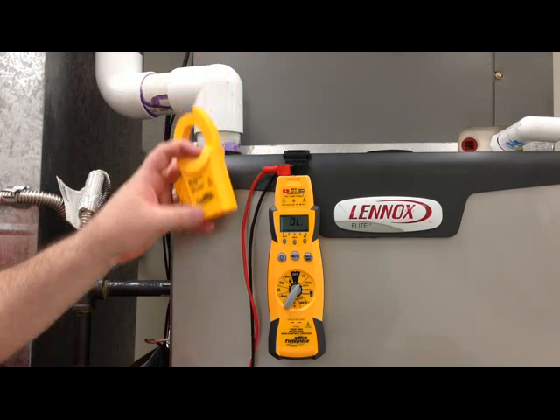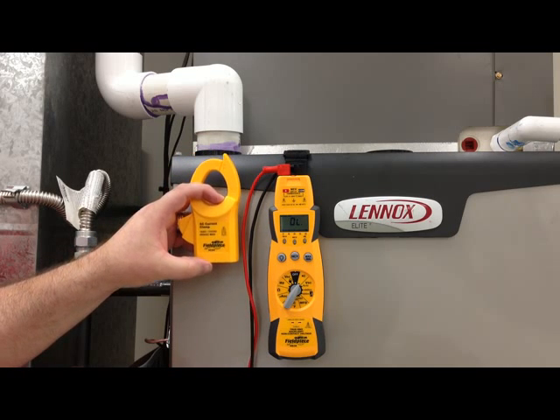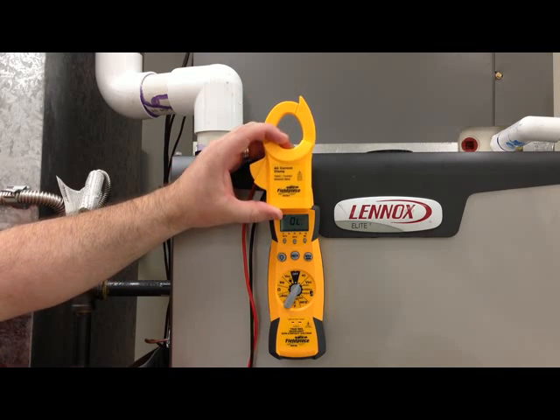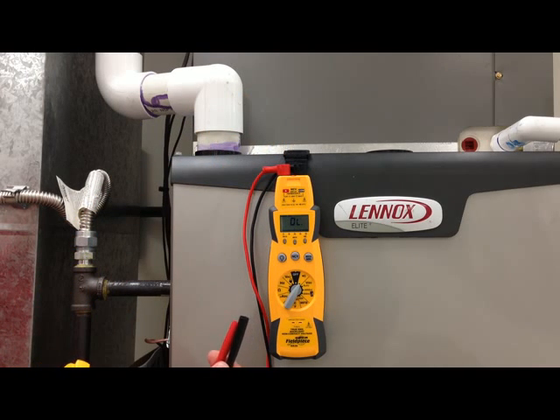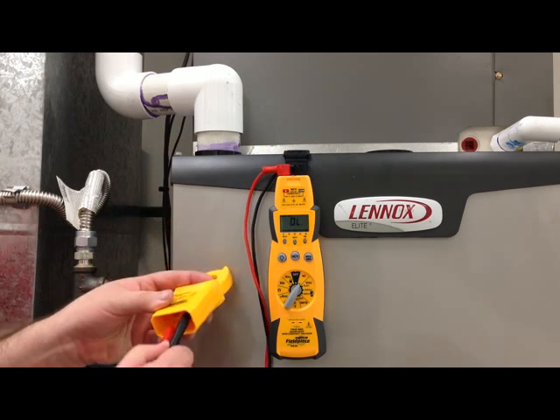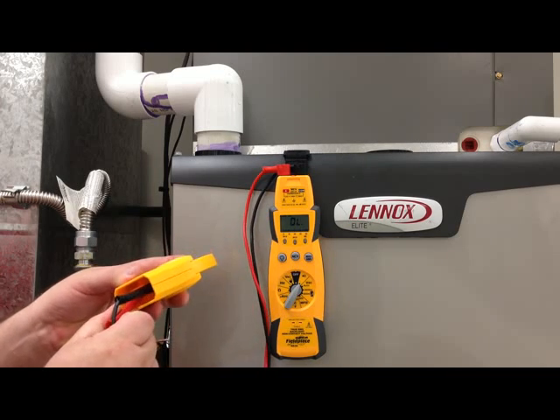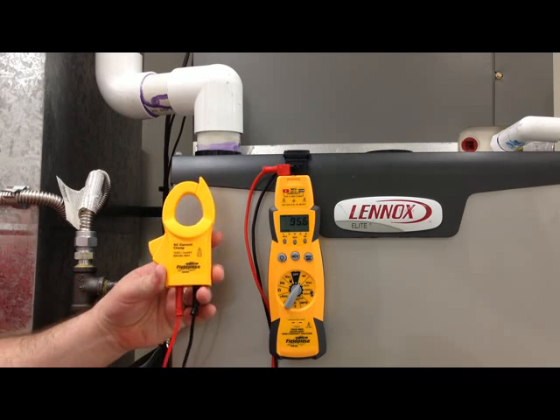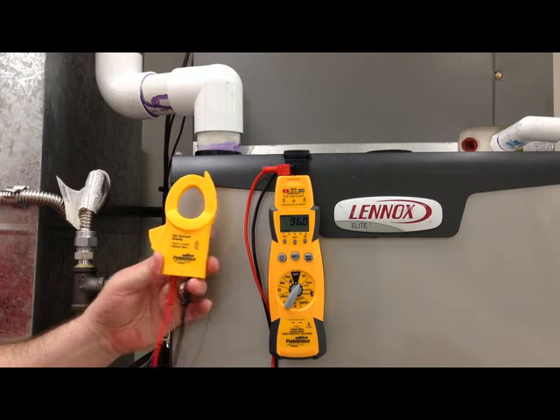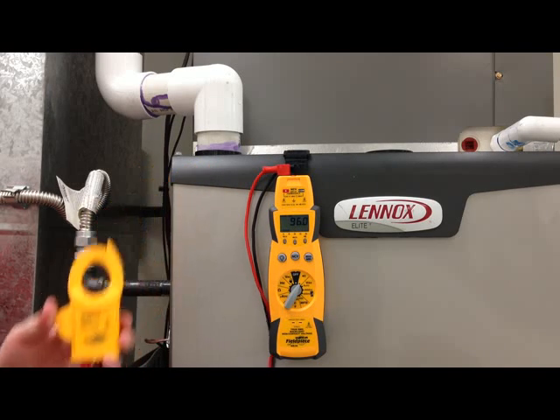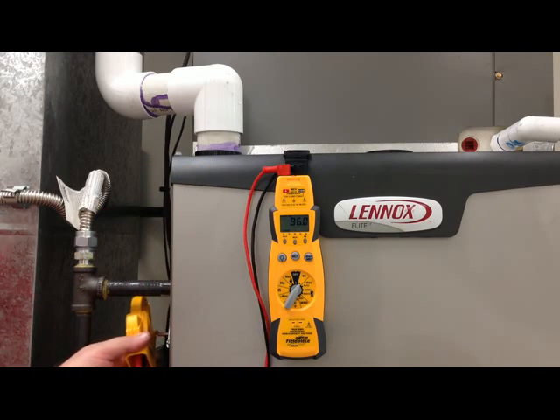One other thing I want to show you is to get to know your meter, because here we have the amp probe connection or the amp clamp connection. We can put it right on top of the meter. Or with a Fieldpiece meter, you can disconnect the tips from your leads and plug them in here so that we can remotely mount the amp meter inside the circuit, put the blower door back on and measure current.